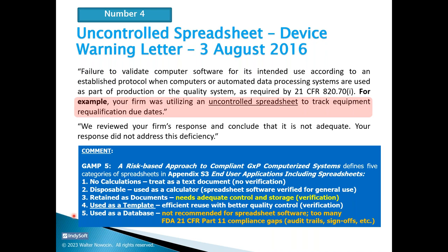And that's because spreadsheets have too many FDA 21 CFR Part 11 compliance gaps. 21 CFR Part 11 is the documentation resource for electronic signatures and electronic records. The expectation is that databases have audit trails, sign-offs, security profiles, and user segregation, and these are all things that spreadsheets don't do very well, or if at all.